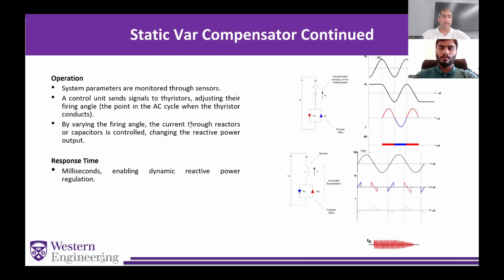So moving on to the next slide, that is about static var compensator operations. Here's how it works. As you can see in the graphs as well, sensors track system voltage, the controller computes the needed vars, and thyristor firing angles modulate current through reactors and capacitors to deliver the exact reactive power required. Because the loop is fully electronic, response is in milliseconds, fast enough to chase down post-fault dips and motor stalling before they snowball. In practice, that speed translates into tighter voltage bands and fewer nuisance trips.